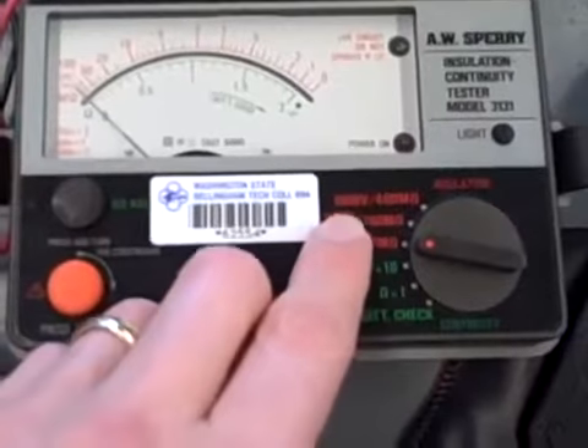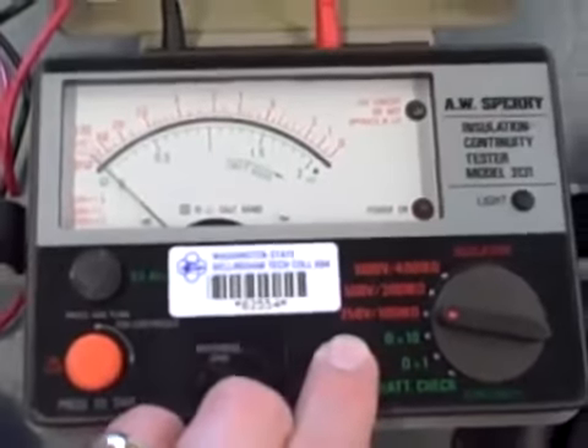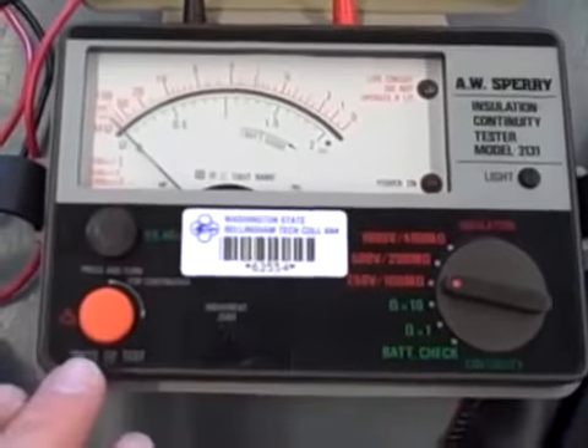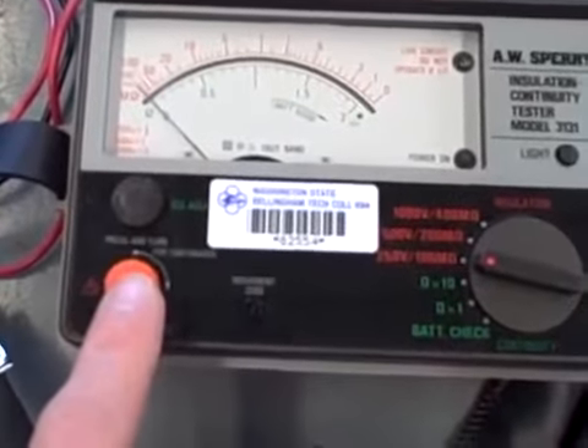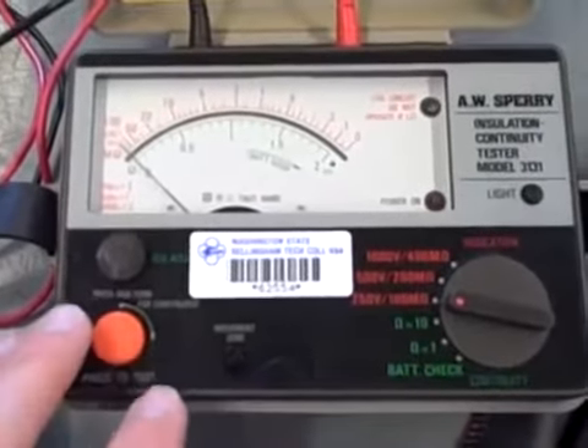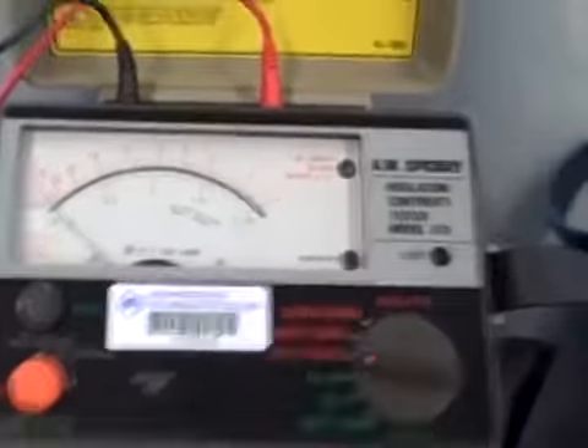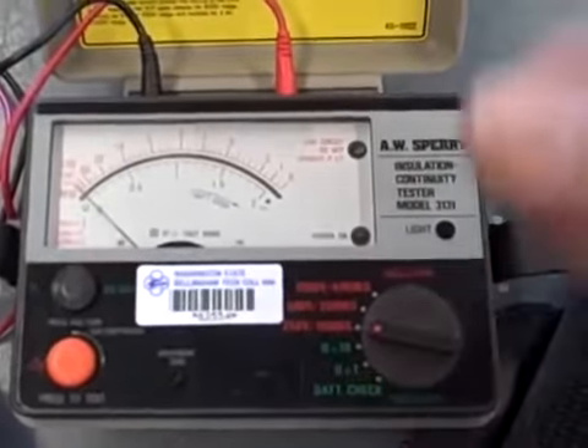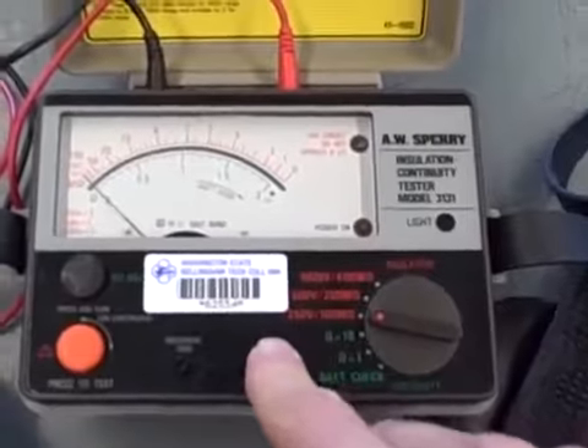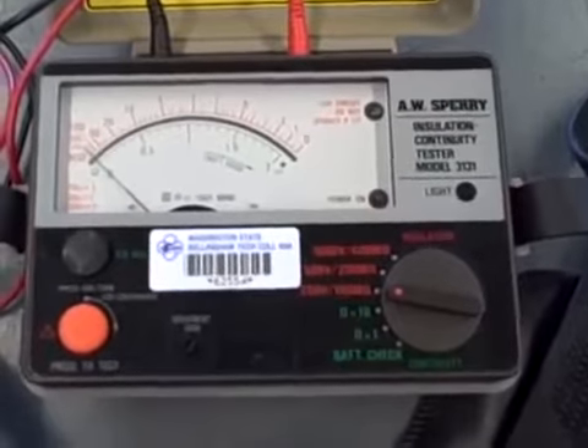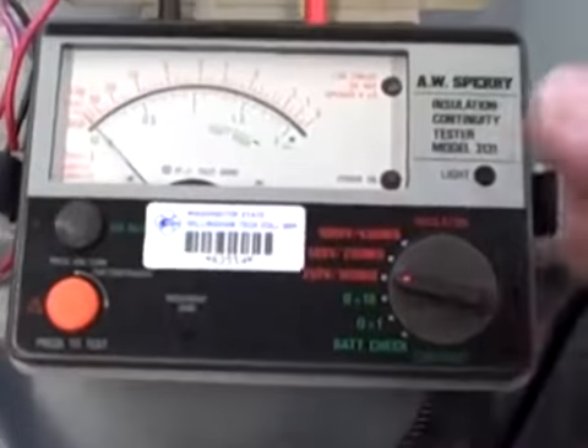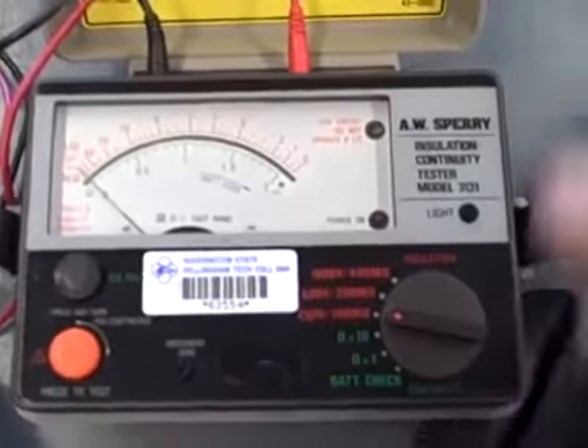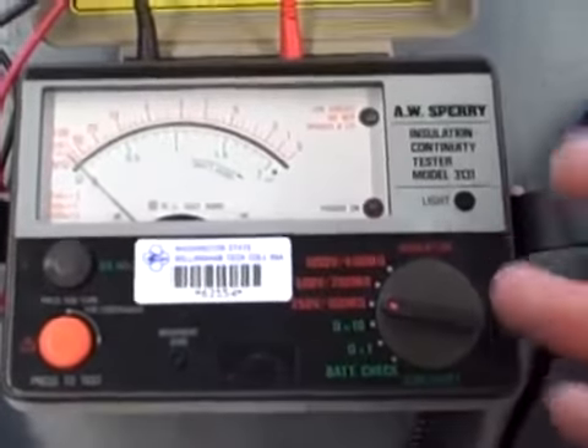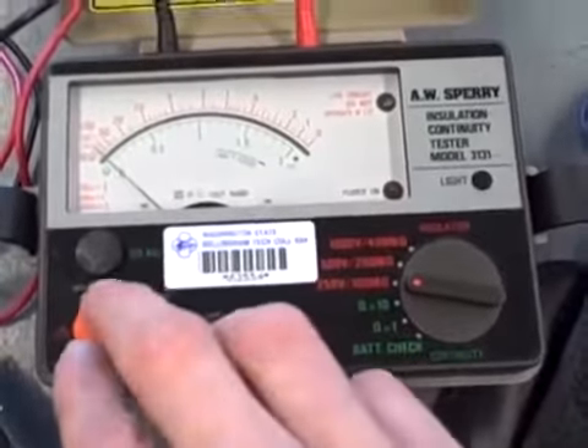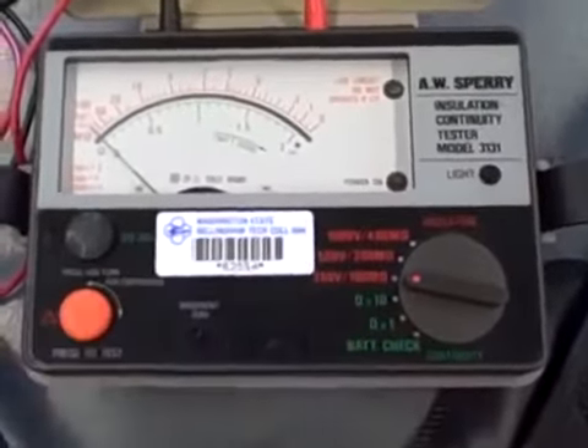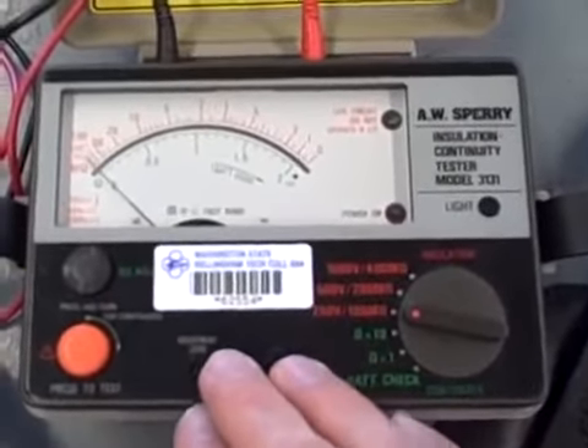It uses a fairly high amount of voltage to do the testing, and yes, this will shock you if you use it incorrectly. This particular model is battery powered, and what you do is you activate the high voltage by pushing the test button. On some of the older devices, especially the ones bearing the name megger, they used to have a hand crank on the side. You would turn a hand crank and it would spin a high voltage DC generator that would generate the power necessary for doing the test. Personally, I prefer the hand crank style because that has a built-in safety feature. You can't shock yourself as you're cranking the hand crank. You'll automatically stop. In this case, it is possible to latch the button in the on position and have it continually produce high voltage. So you need to be very careful with an instrument like this when you're using it.